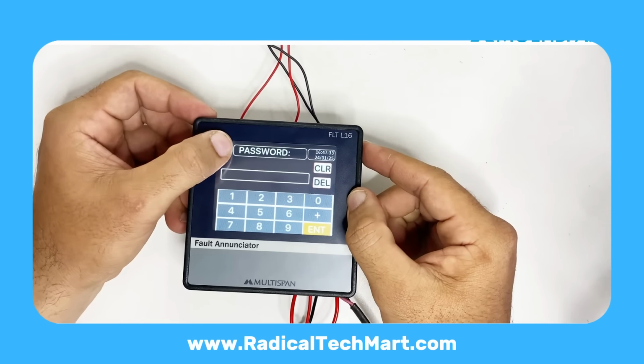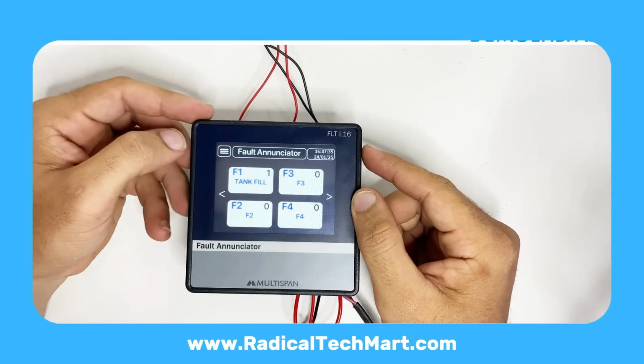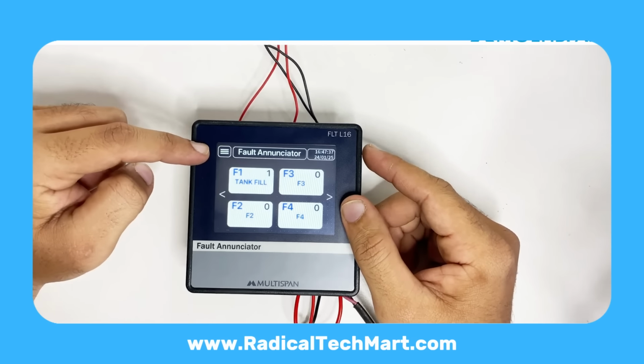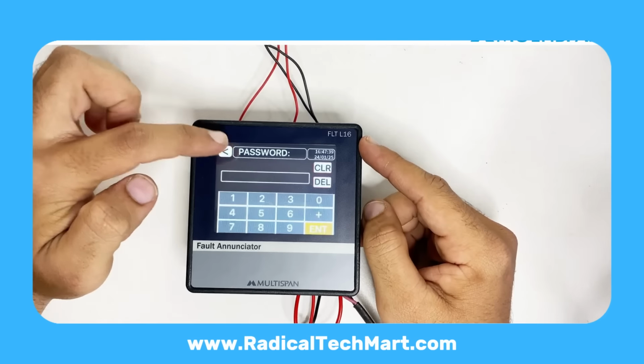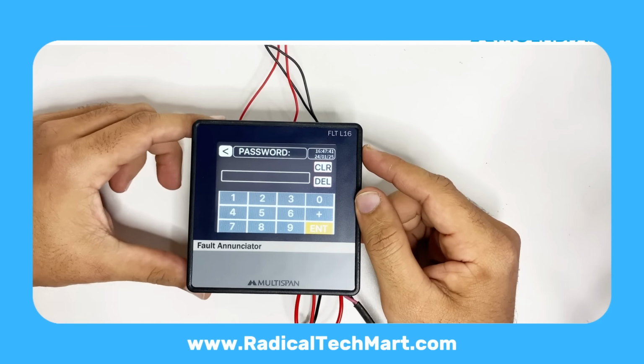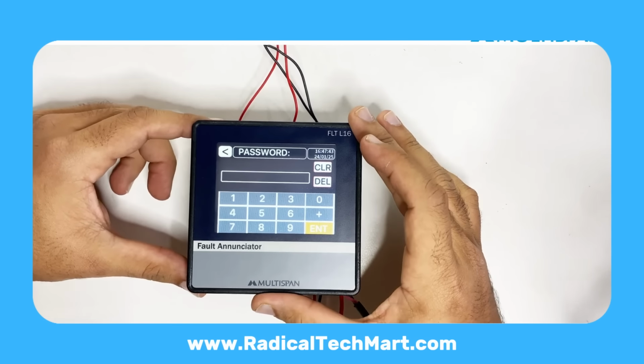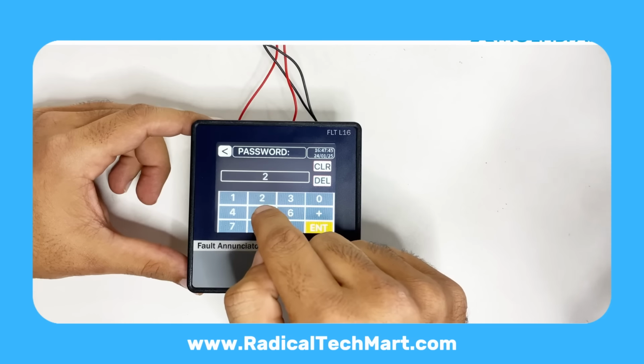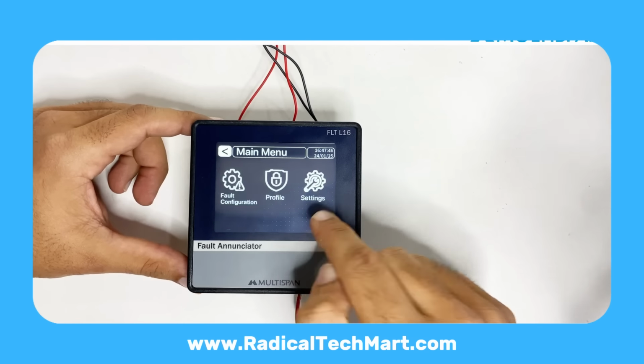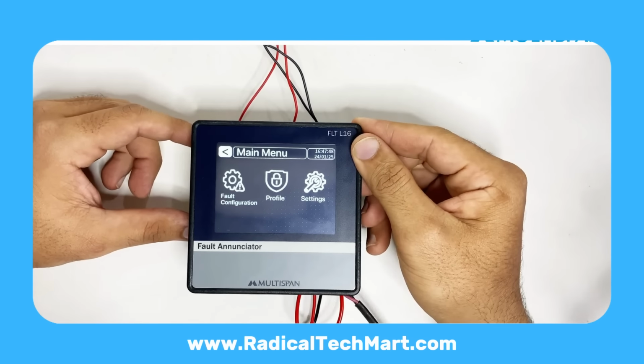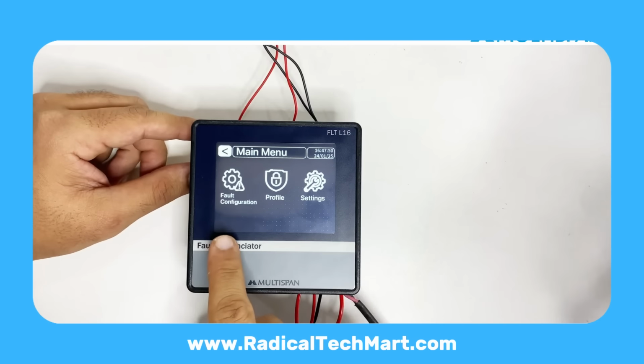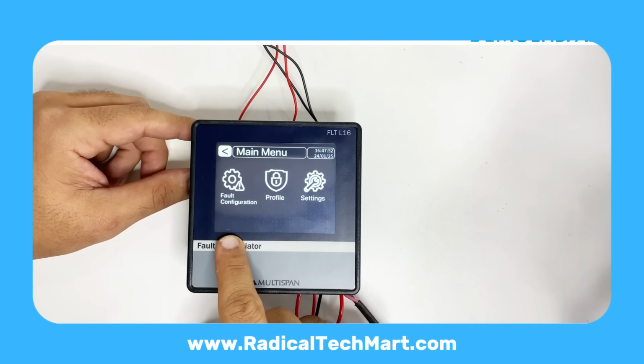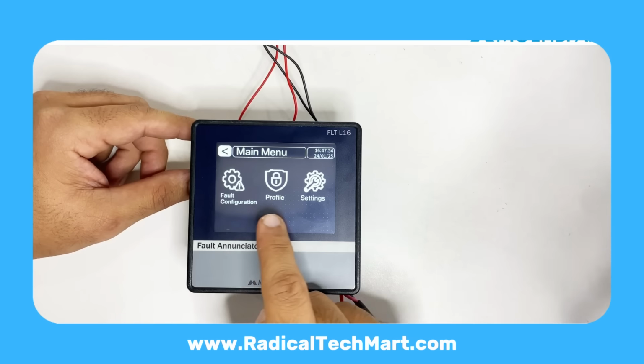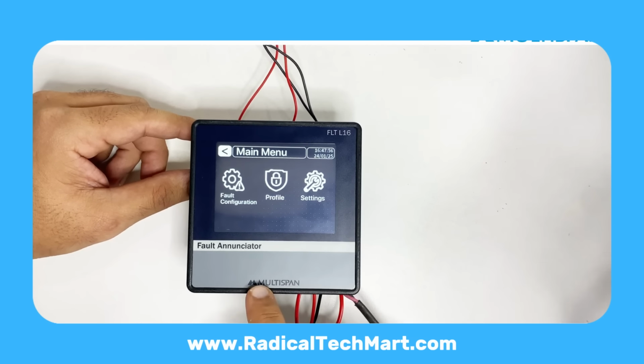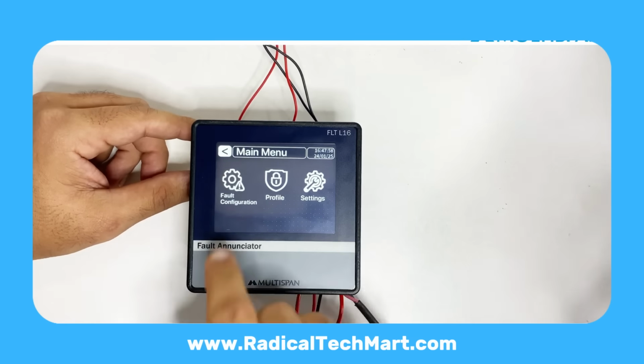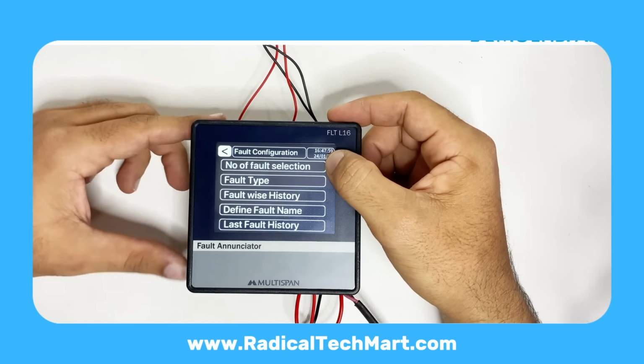On the front panel, to go inside the menu, we have a menu button at the left corner. When I press it, the display first asks for a password. Because this device is password protected, the default password is 25. After entering 25 and pressing enter, the main menu opens. Here, we get three main sections: fault config, profile, and settings. Let's start with fault config.